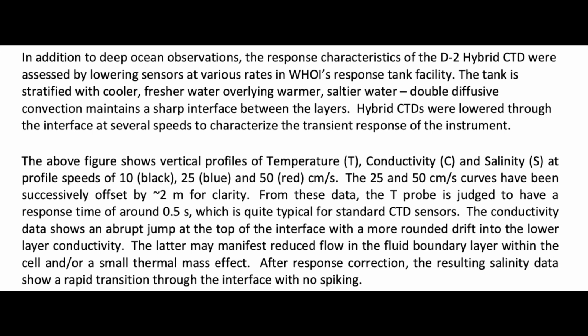The 25 and 50 centimeters per second curves have been offset by around 2 meters for clarity. From these data, the T-probe is judged to have a response time of around 0.5 seconds, which is quite typical for standard CTD sensors. The conductivity data shows an abrupt jump at the top of the interface with a more rounded drift into the lower layer conductivity. The latter may manifest reduced flow in the fluid boundary layer within the cell and/or a small thermal mass effect. After response correction, the resulting salinity data show a rapid transition through the interface with no spiking.